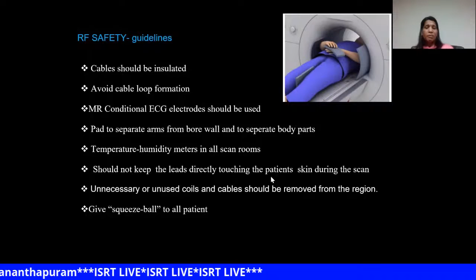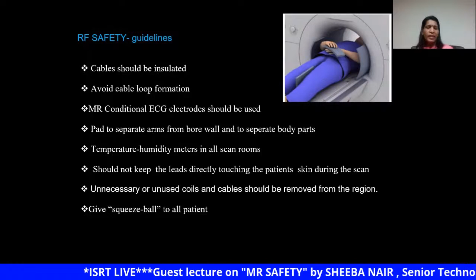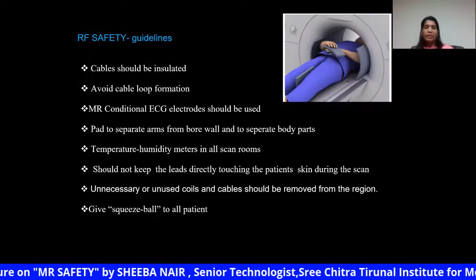Use RF pads to separate the body part from the bore, and keep RF pads between the body parts. There should be temperature and humidity meters in the MR scanner room. Also avoid the leads or any other monitoring device touching the patient's skin directly. If you are not using any coils or cables, don't keep them in the region of interest. Instead, remove them, and always give a squeeze ball to the patient, and respond immediately once the patient presses the squeeze ball.